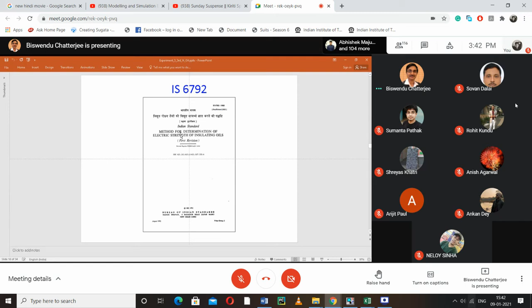IS 6792 tells how you will determine the electric strength for insulating oil. By this standard, we will do that. The test method comprises subjecting the oil in a specific apparatus. You cannot do it in your arbitrary way, again it is a standard. So again, like paper, an AC electric field is applied, continuously increasing voltage till the oil breaks down. We will note that. See here how the test apparatus looks like.